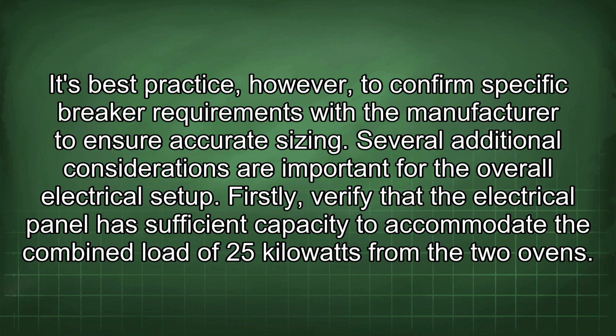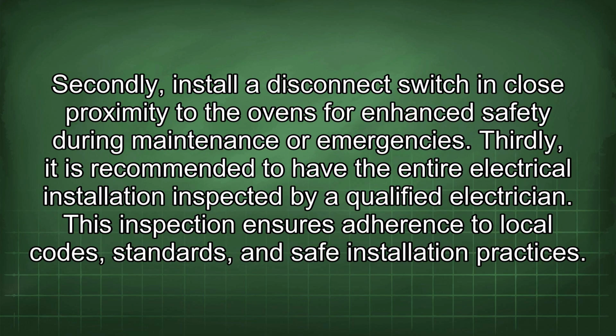Several additional considerations are important for the overall electrical setup. Firstly, verify that the electrical panel has sufficient capacity to accommodate the combined load of 25 kilowatts from the two ovens. Secondly, install a disconnect switch in close proximity to the ovens for enhanced safety during maintenance or emergencies. Thirdly, it is recommended to have the entire electrical installation inspected by a qualified electrician. This inspection ensures adherence to local codes, standards, and safe installation practices.